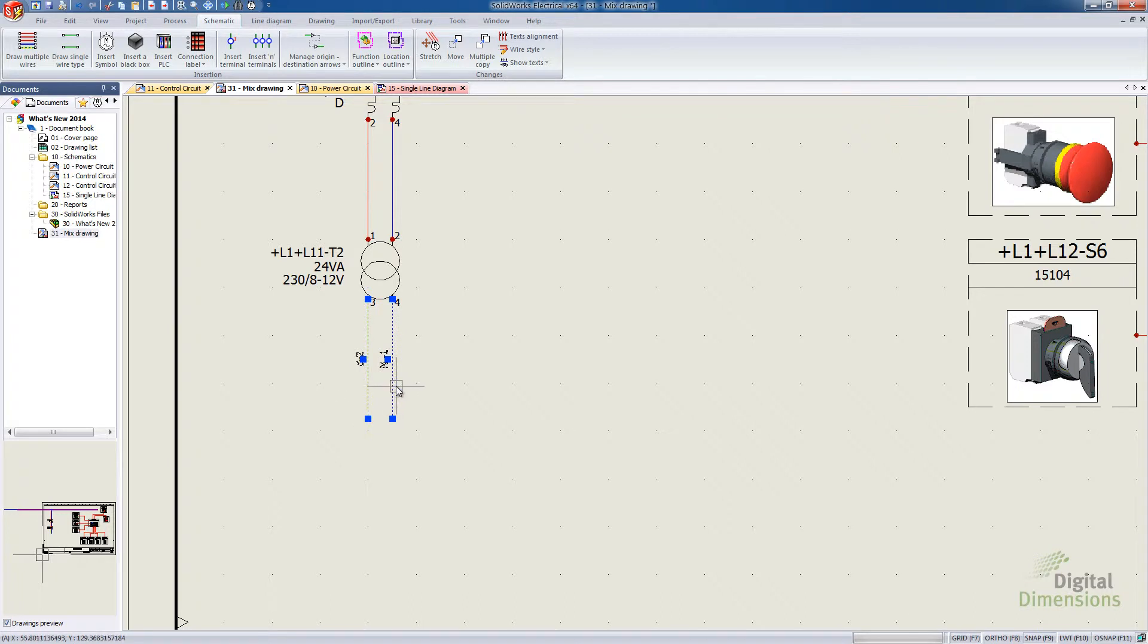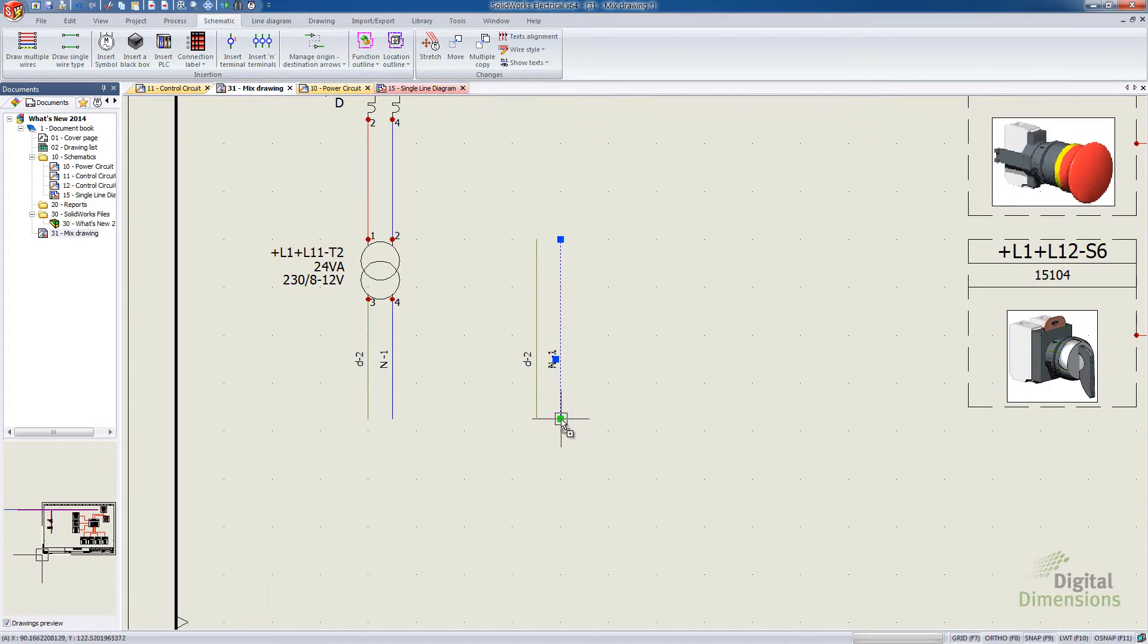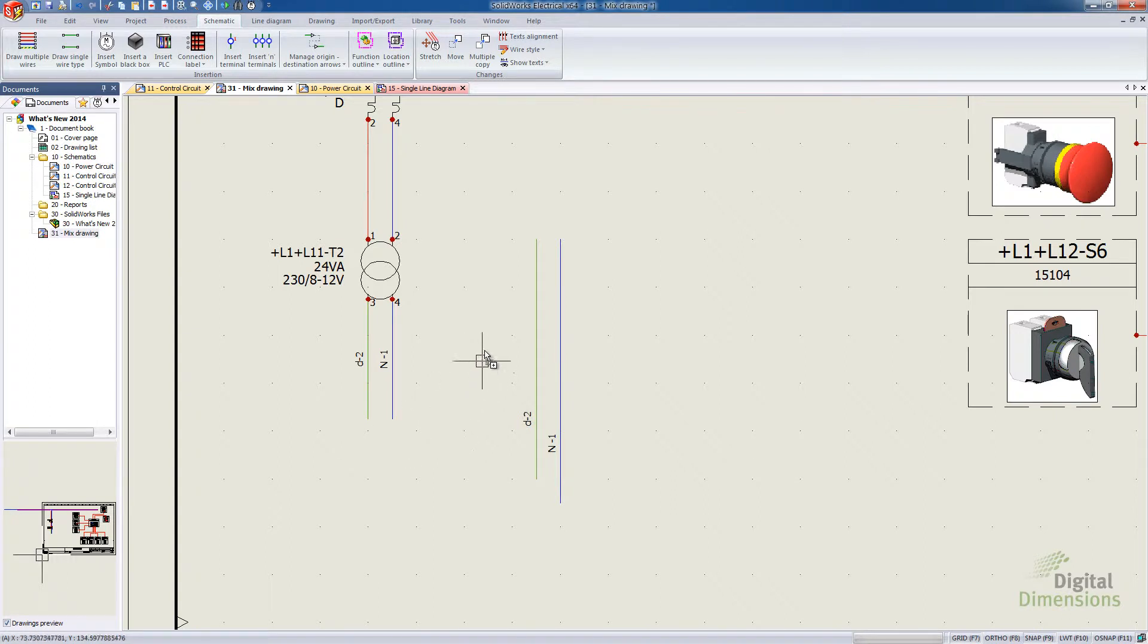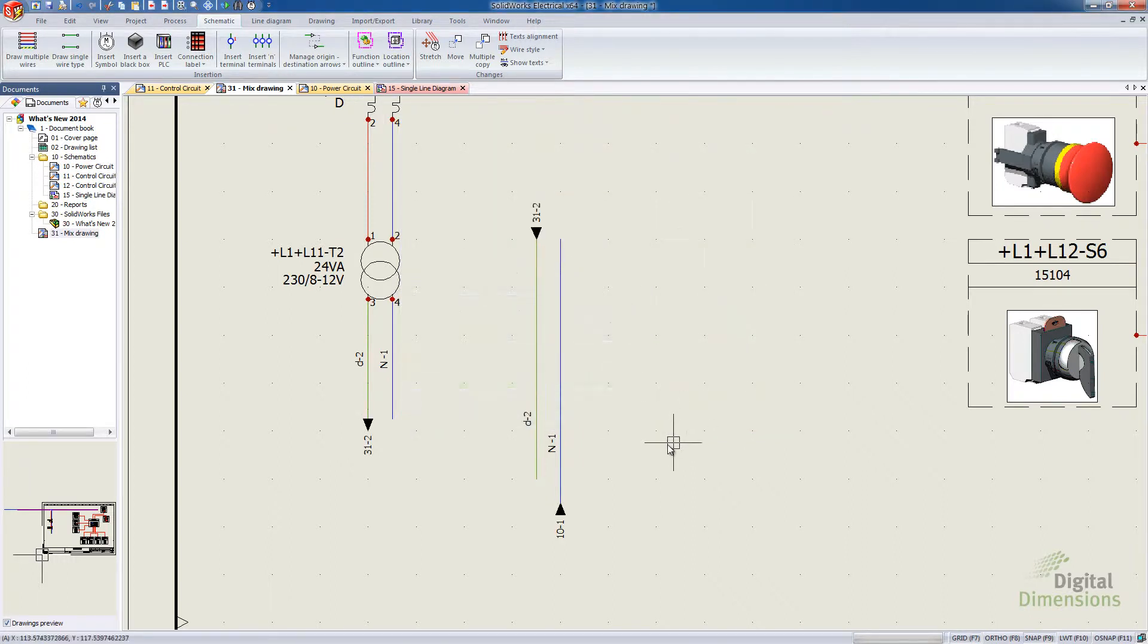I'll make copies of them. So I'm going to grab them, hold Control, and then drag to make copies. I'm going to extend these up a little bit just for the heck of it. And I'll extend those down a little bit. And the way this functionality works is it goes from top to bottom, left to right as far as the origin destination marks. Where this option shows up at is if you hit the down arrow or the bottom half of the Manage Origin Destinations. I'm going to go Automatic Insertion. It allows us to pick out which symbol that we want. And we can do Whole Project, Current Book, or Choose a Scheme. But I'm going to go Whole Project, Auto Connect. I'll hit OK.